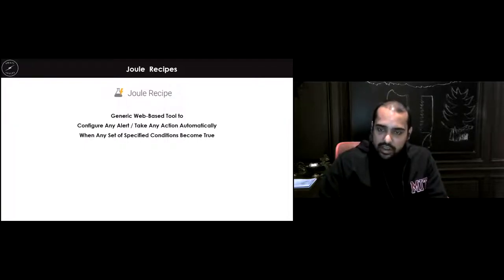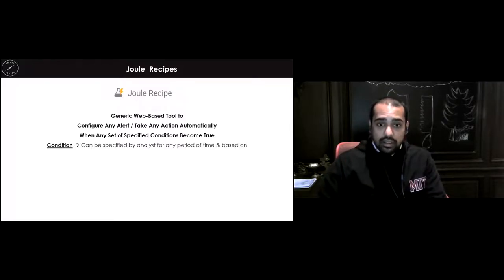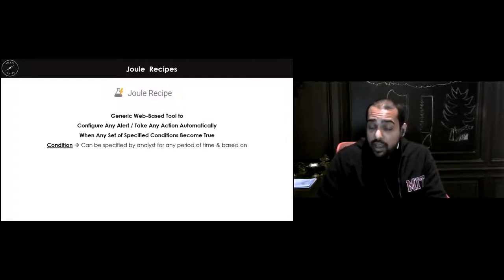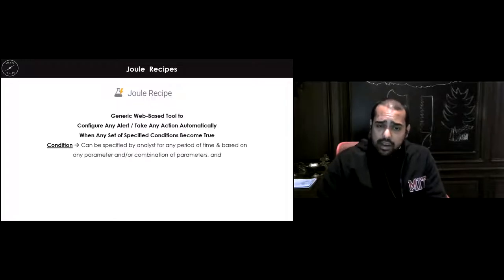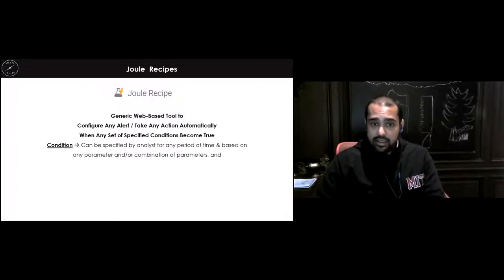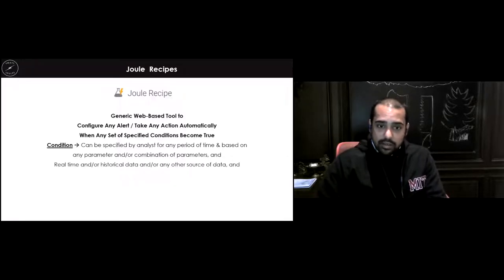When any set of specified conditions become true, it automatically takes actions in terms of alerts or start, stop, or changing speeds, etc. These conditions can be specified by any analyst, anybody who knows how to use Google or Facebook. It's so simple, the user interface. These conditions can be specified for any period of time, and they can be based on any parameter or any combination of parameters, and they can be real-time, historical data or any other source of data. They don't even need to be the data that is already stored in the IoT platform. They can take in data from anywhere, and the conditions can be based on any single logic or a combination of logic.